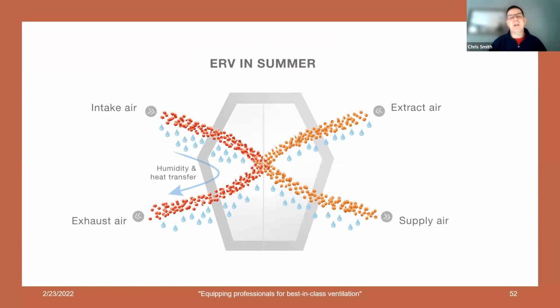In the summertime, in a hot, humid scenario, the ERV is also valuable because it's able to reject a lot of that outdoor humidity as well as the heat. Basically, the cooler, drier indoor air is going to pull heat and humidity from the outdoor air inside the heat exchanger, and as it's exhausted outside of the house, it's going to deliver more of that heat and humidity to the outside of the house. The fresh air that comes into the house will be close to room temperature and will have given up a lot of the outdoor humidity. So it comes in fairly comfortable.